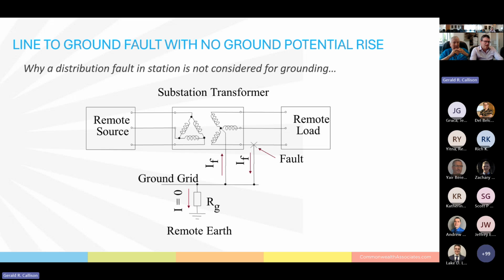So whenever we have current whose source is coming from the neutral through a grounded Y, we don't consider that in grounding design because it doesn't affect GPR. And the reason for that is that it does not enter the grid to soil interface.